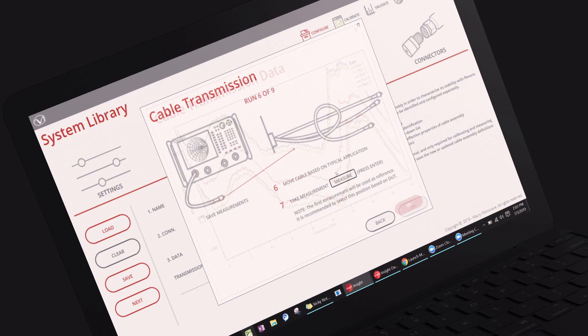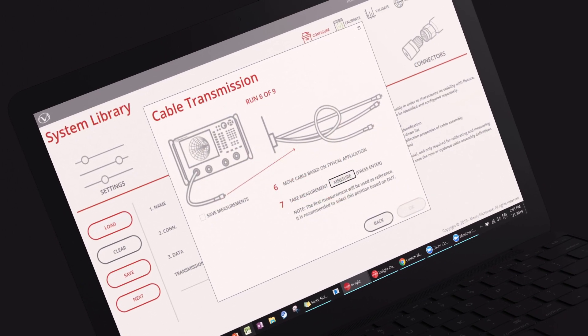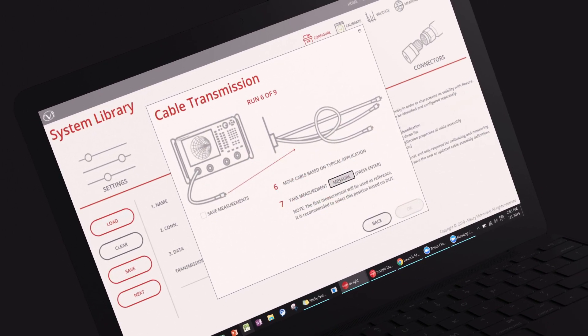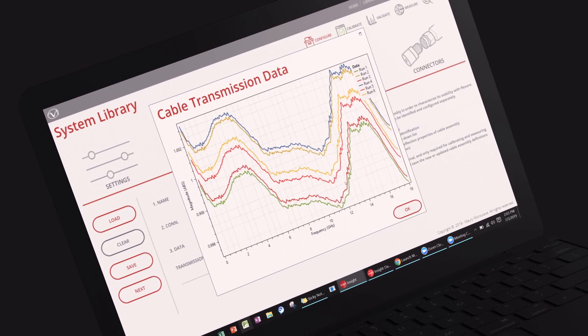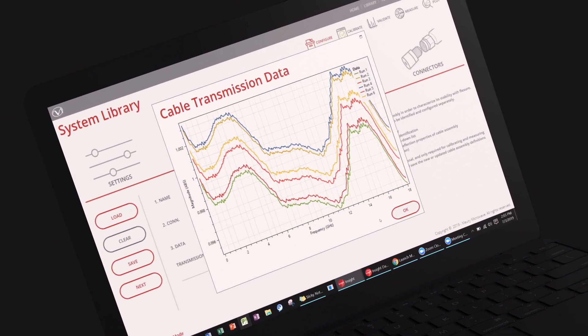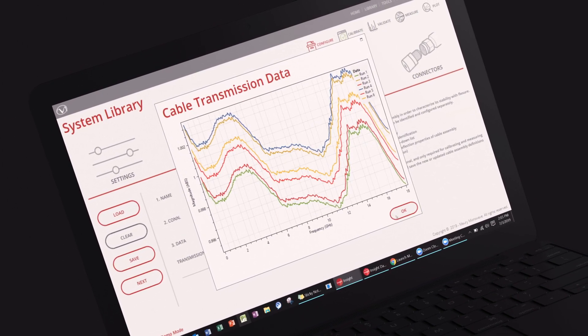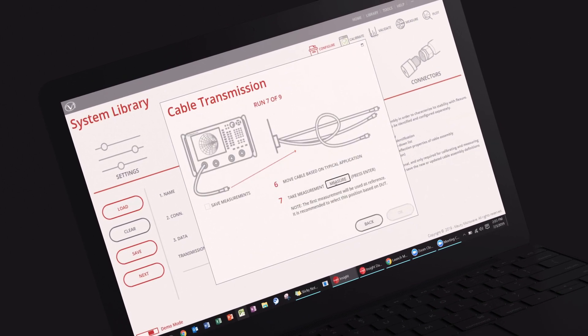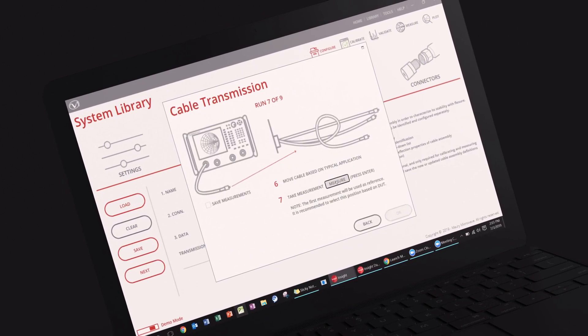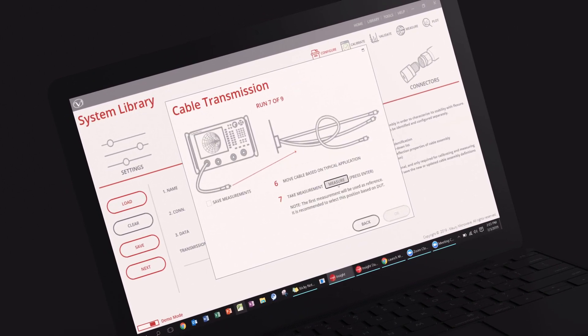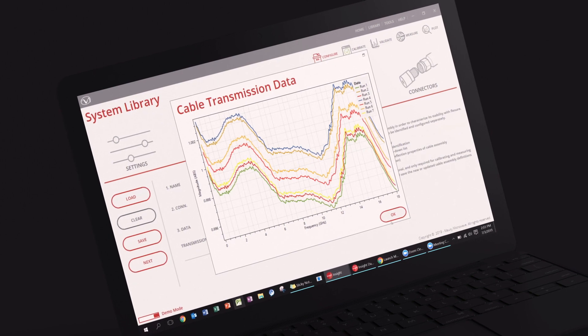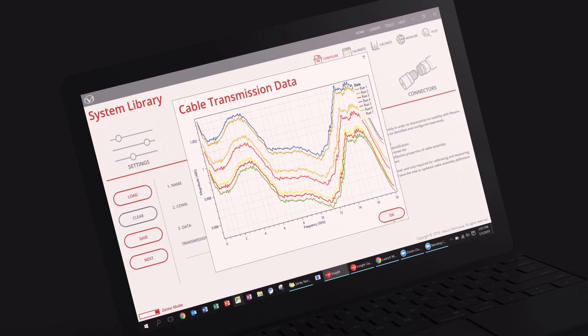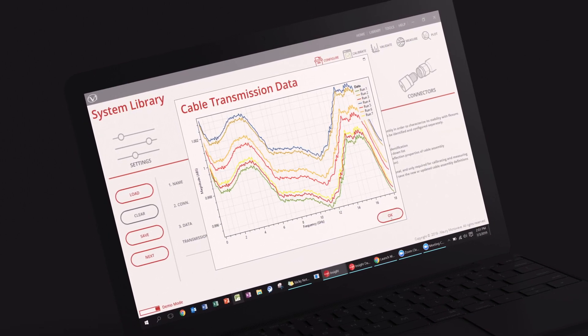Measurement uncertainties caused by cable flexure can be characterized using Insight. Cable transmission uncertainty is characterized by connecting a short circuit termination to the end of the cable and performing multiple measurements while bending the cable.